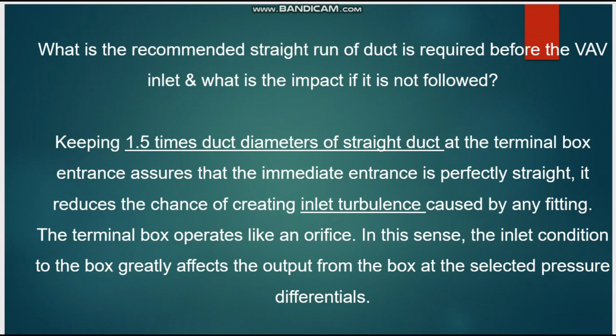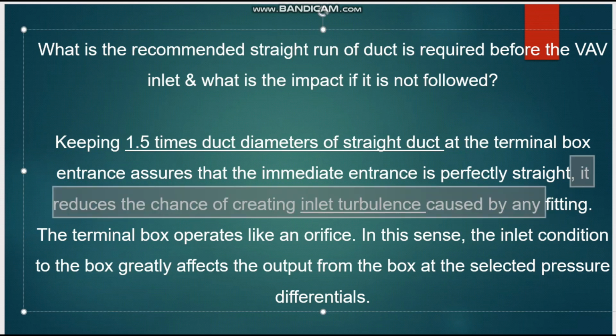Okay, at the end, like this you can see here. So 200 mm means 1.5 into 200, so 300 mm of straight duct must be there before the VAV. Okay, so it reduces the chance of creating inlet turbulence caused by any fittings, whether it is an elbow or any other fittings. It will create inlet turbulence at the starting point of the VAV. So we have to avoid that.